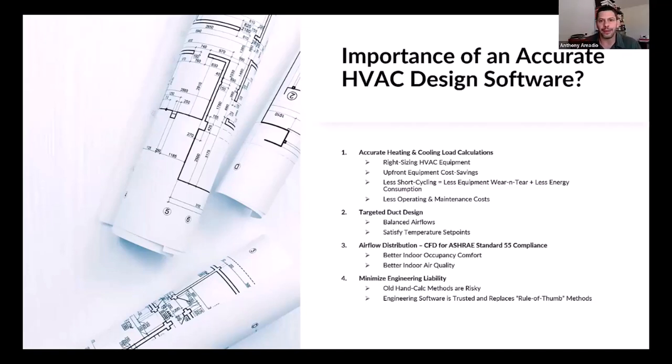Before, I was doing ADPI hand calcs. So, it's kind of generic for a box of 9-foot or 10-foot ceiling heights, and assuming my diffuser was going to be in the center of the space, but maybe there's lighting in the way. And a lot of times people are using 24 by 24 ceiling grills. But if we have a little bit of CFM, we're just going to be dumping cold air on somebody. Having a smaller grill or register, getting more throw out and stuff like that. ADPI was a good guide, but it still didn't even really ensure occupant comfort.